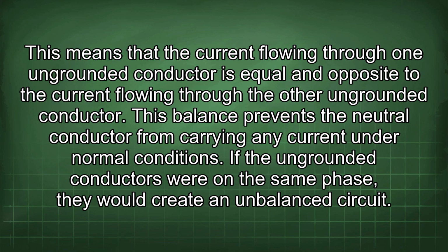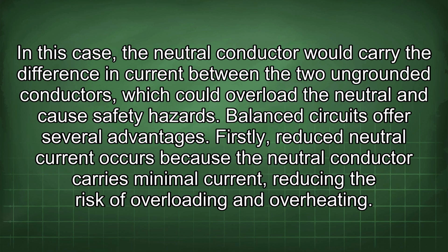If the ungrounded conductors were on the same phase, they would create an imbalanced circuit. In this case, the neutral conductor would carry the difference in current between the 2 ungrounded conductors, which could overload the neutral and cause safety hazards.